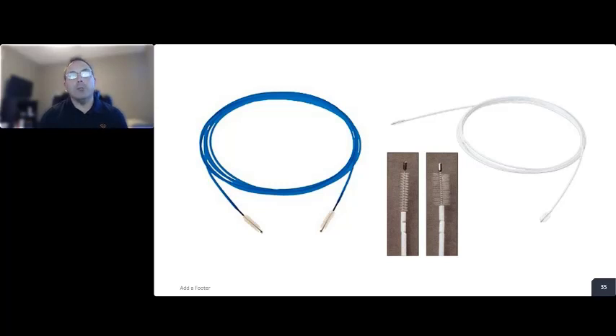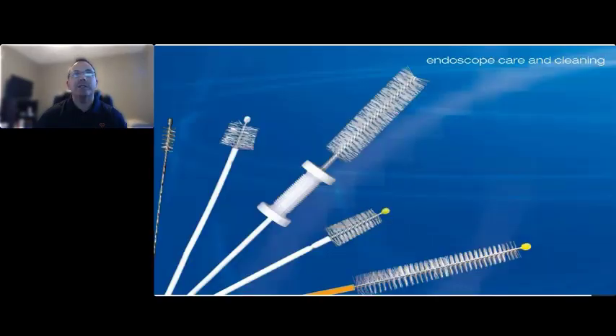Having a tip on a brush that is cleaning stainless steel is not necessary, because the wire twist or any of these that are made with brushes is a much softer metal. They won't damage the inside of your stainless steel. Conversely, the material that is used for the inside of channels in flexible endoscopes could easily be damaged by stainless steel. Any brush we ever put down a flexible endoscope needs to have a tip on it. These are designed to protect the inside of those channels and not cut them and allow fluid invasion. But again, there's many, many different styles of these tips that we're going to see. I can't tell you one is better than the other.